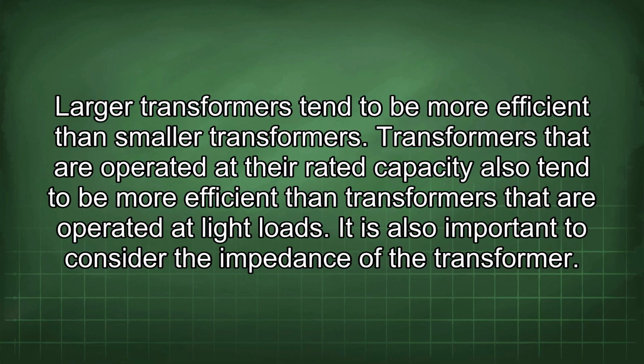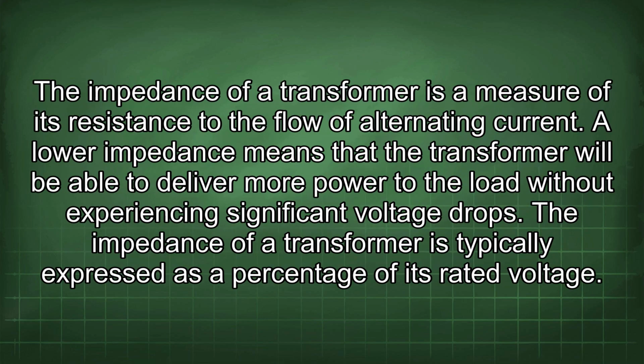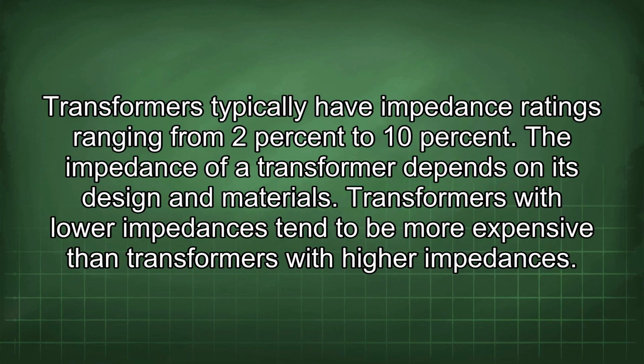It is also important to consider the impedance of the transformer. The impedance of a transformer is a measure of its resistance to the flow of alternating current. A lower impedance means that the transformer will be able to deliver more power to the load without experiencing significant voltage drops. The impedance of a transformer is typically expressed as a percentage of its rated voltage. Transformers typically have impedance ratings ranging from 2% to 10%. The impedance of a transformer depends on its design and materials. Transformers with lower impedances tend to be more expensive than transformers with higher impedances.